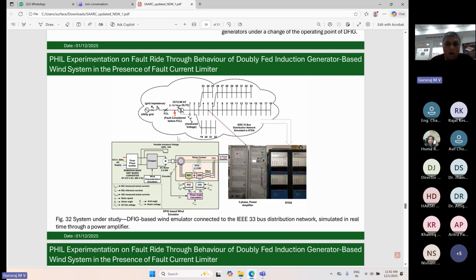So especially in this work, we have considered a specific case scenario where the fault is assumed to take place before the fault current limiter. Various hardware and software solutions have been reported in the literature, where the researchers indicate that having a fault current limiter after the DFIG may address the problem to a certain extent. But if, for some reason, this fault current limiter is situated far away from the DFIG to have better protection coordination, then the fault can happen before the fault current limiter, in between the fault current limiter and the DFIG. So instead of supporting the system, the very presence of the fault current limiter may deteriorate the condition.